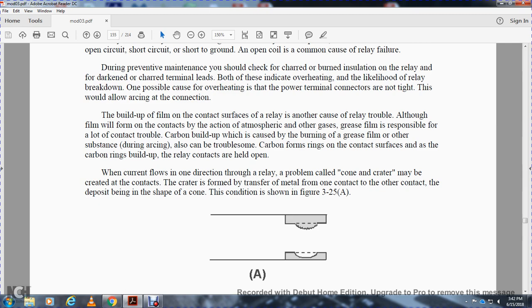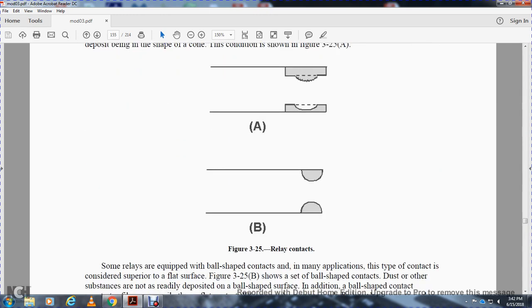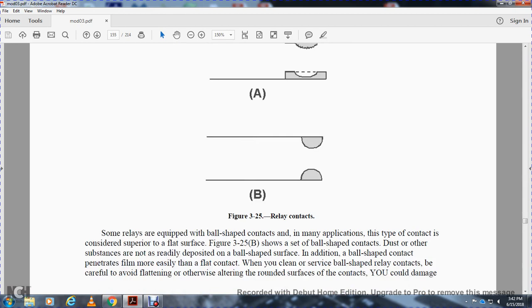When current flows in one direction through the relay, a problem called cone and crater may be created at the contacts. Craters form with the transfer of metal from one contact to the other, depositing it in the shape of a cone. The condition is shown in Figure 3-25A. Some relays are equipped with ball-shaped contacts. In most applications, this type of contactor is considered superior to a flat surface. Figure 3-25B shows a set of ball-shaped contacts. Oil and other substances do not readily deposit on the ball-shaped surfaces.